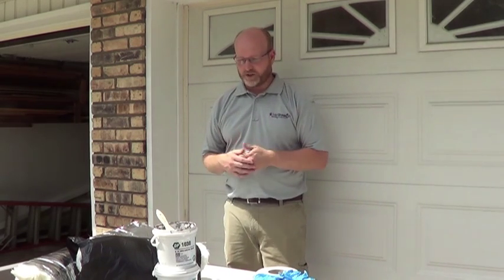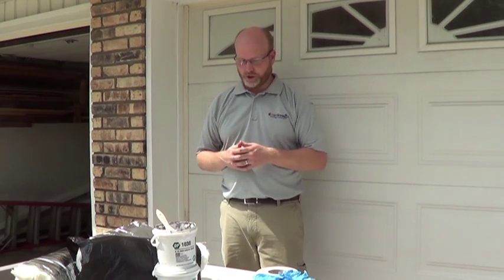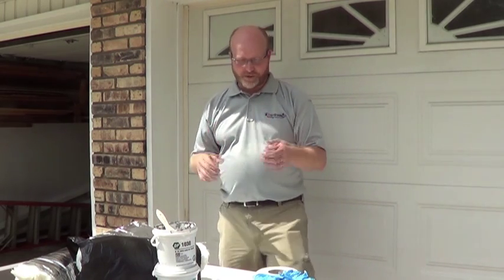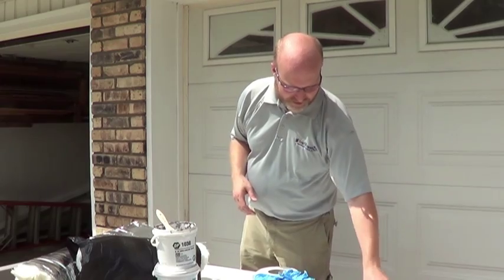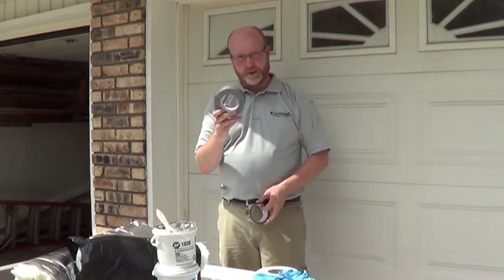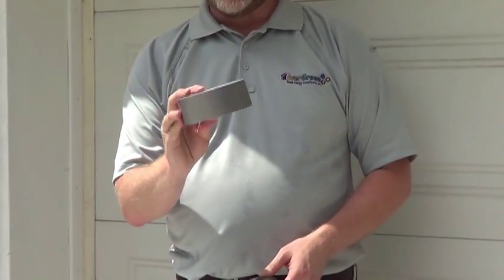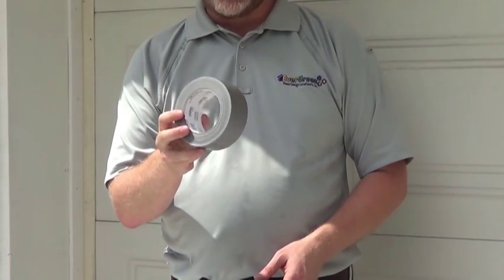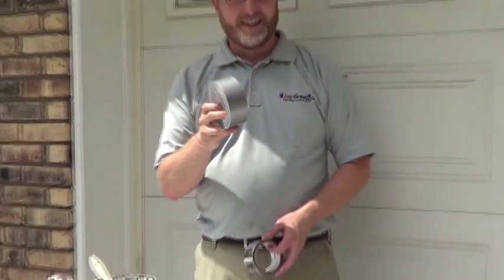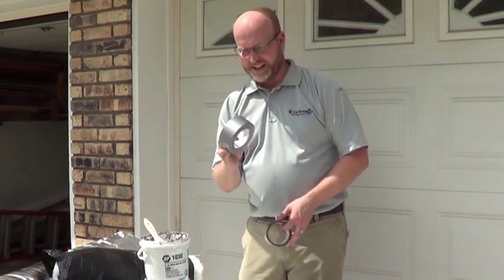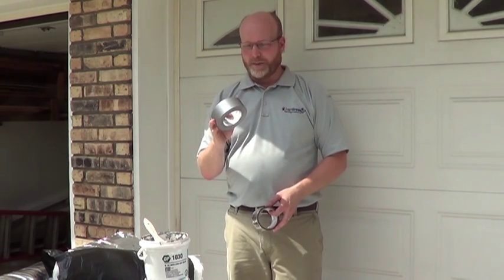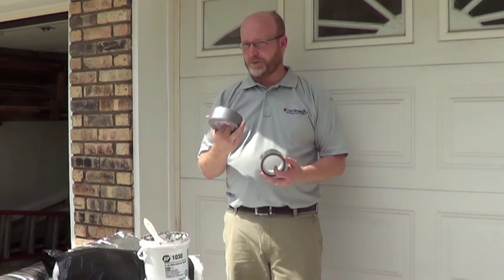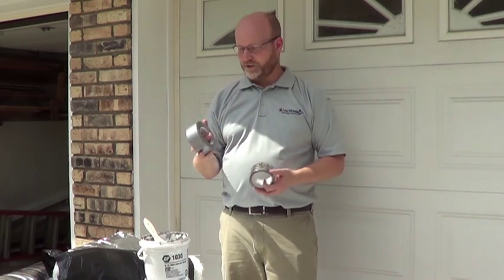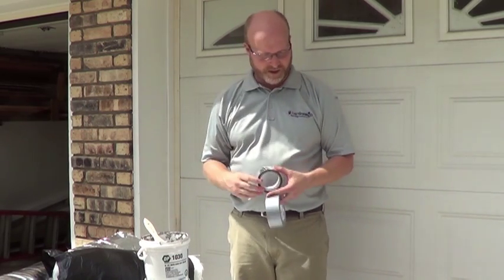Now, a lot of duct sealing you can do on your own, or you can hire a contractor to do that. But today we're going to show you some simple tips to seal your own ductwork. A couple different materials we use to seal ducts. You may have seen people use duct tape. The joke in my industry is that we use duct tape for anything except ductwork. It actually does not adhere well to the ductwork, and over time it becomes brittle and dry and peels right off. So you lose the benefit of the sealing by using duct tape.